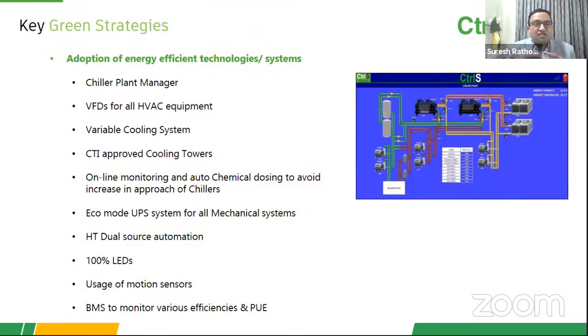Some of the other green initiatives are choosing each and every piece of equipment in the data center so that it lowers energy consumption, improves our PUE, and contributes to the betterment of this world. We have a chiller plant manager, and all chillers are managed with it. It could be run separately as well, but a conscious decision was taken right from day one that each and every chiller in the data center will be run with the chiller plant manager. That brings more efficiency. We have variable frequency drives for all the HVAC equipment, and a variable cooling system. All the cooling towers are interfaced with the CTI, with online monitoring and chemical dosing of every chiller.